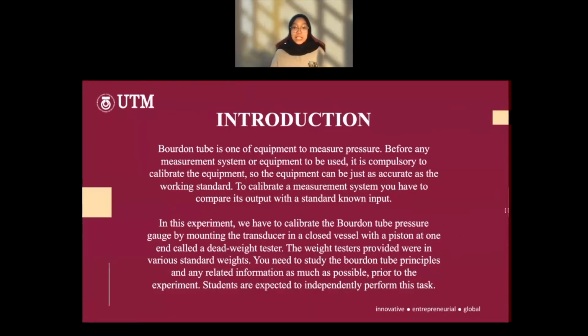Now I will explain the introduction. The Bourdon tube is one of the equipment used to measure pressure. Before any measurement system or equipment is used, it is compulsory to calibrate it so that it can be just as accurate as the working standard. To calibrate a measurement system, you have to compare its output with the standard known input.